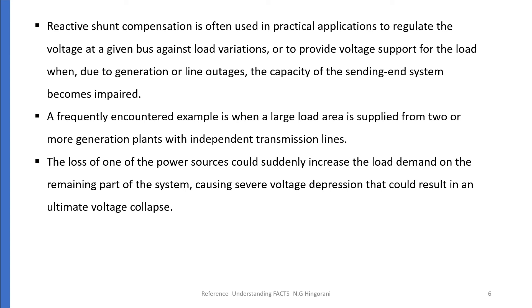The loss of one of the power sources could suddenly increase the load demand on the remaining part of the system, causing severe voltage depression that could result in an ultimate voltage collapse. So in order to avoid such situations for a radial long transmission line, shunt compensation is provided at the load end. This is one of the applications of shunt compensation.